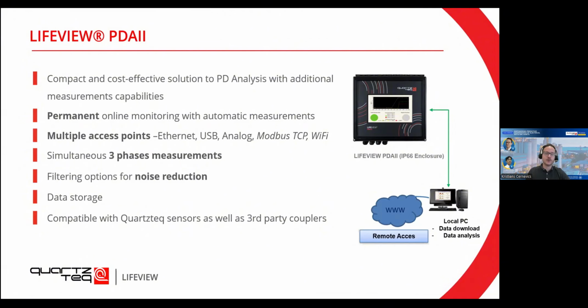This tool gives you multiple access points. You can access through Ethernet, USB, analog, Modbus, or Wi-Fi. So many, many different options of how you want to access the data. It does measurements simultaneously on the 3 phases. And it also has filtering options for noise reduction. So noise reduction in partial discharges is a very big topic because what you want to see is just the discharges, not the noise. The PDA2 also gives you the option to store the data, so you can see what has happened with your machine over a period of months and years.